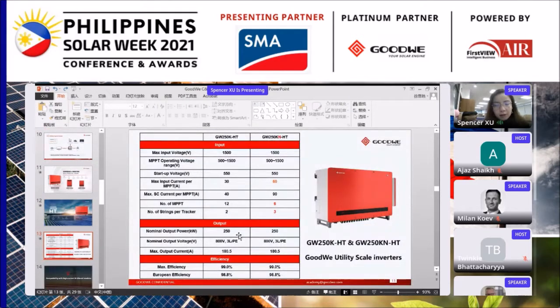Here we have a special version, the KN series. It is specially designed for the 210mm PV modules. The main difference is that the KN series will have 6 MPPTs, and each MPPT will have 3 strings, and each string will have a maximum 20 ampere input current, so that it can fit the large current trend of the PV modules.